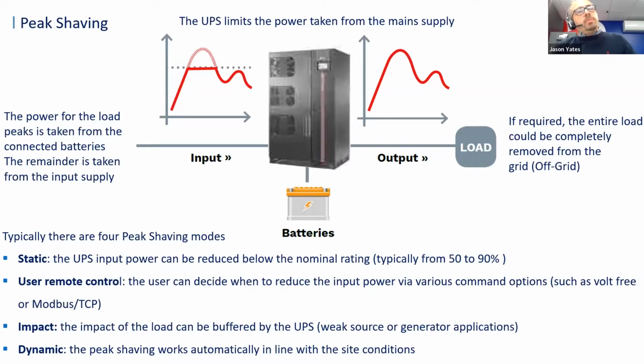Now, typically there are 4 peak shaving modes of operation. The first one is a static load, whereby the UPS input has a fixed and defined level, and the system just sits there and peak shaves to that set point. You can take that one step further, whereby the user can control and decide when the UPS system limits that power, and this command can be pushed through to the UPS either via volt-free contacts or Modbus TCP, etc.